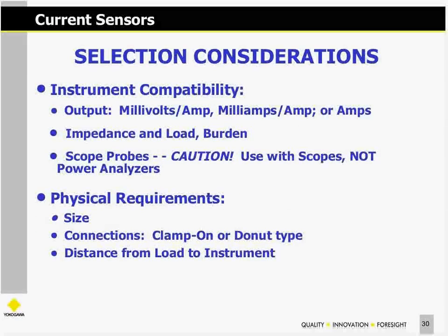The other thing you have to look at is instrument compatibility. What's the output of that current sensor? Some of them are millivolts per amp, some milliamps, or a standard current output. Then we have to look at the impedance, which is the load or burden on the CT.